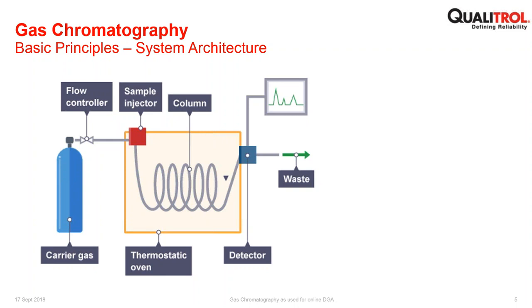There is a place to introduce a sample, and in our case, it's a sample of the gases that have been extracted from transformer oil, but there are many applications for gas chromatography outside of dissolved gas analysis, and I have a slide just showing a few of those. There is a column, and this column, as illustrated here, is a long tube. It can be stainless steel, it can be glass, it can be very narrow bore in the form of a capillary tube, or it can be wider bore, perhaps 1 millimeter, in the form of a stainless steel tube. It is contained inside an oven, and that oven has some thermostatic programming. So it's either held at a static temperature, or its temperature is raised or lowered depending on the application.